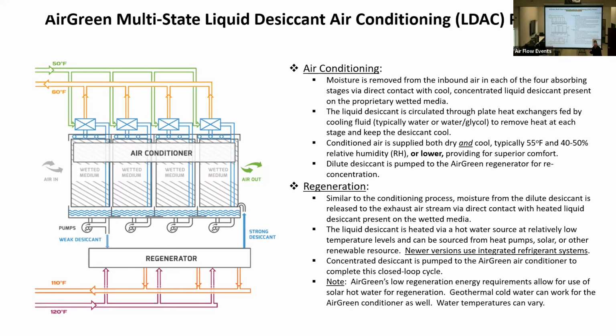So for an indoor grow facility, where they put all the units outside adjacent to each individual grow room, the regenerator sits outside and it just circulates the outside air through it. It regenerates. One of the things I didn't realize is one of the projects we're actually being compared directly, and that's the subject of the ASHRAE paper here, compared directly with the performance of another vendor's solid desiccant system. It's all energy metered. It's an Exotech system, if you're familiar with them.